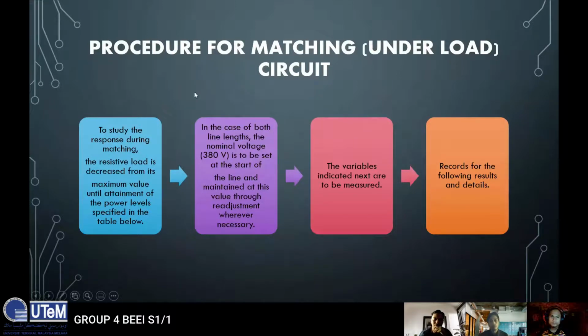Okay, for the procedure for matching under load circuit, first, to study the response during matching, the resistive load is decreased from its maximum value until attainment of the power levels specified in the table below. Then, in the case of both line lengths, the nominal voltage 380 volt is to be set at the start of the line and maintained at this value, adjusting whenever necessary. Next, the variables indicated are to be measured. Then, record the following results and details.